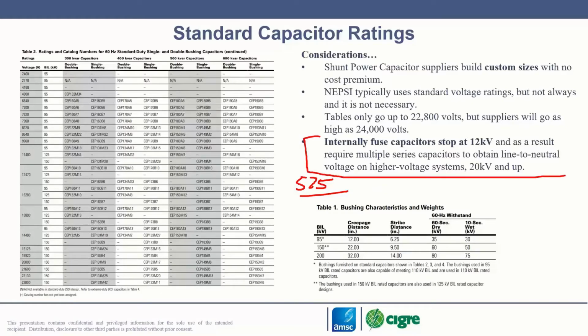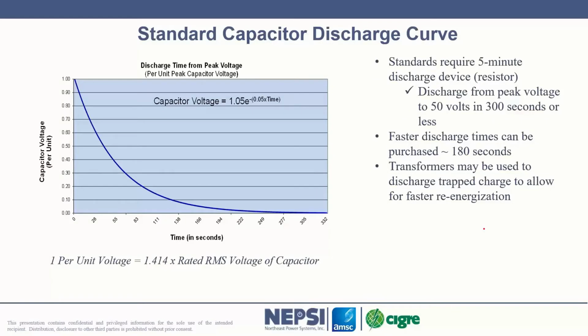Internally fused capacitors are interesting to note. Typically, we're dealing with voltages that stop at about 12 kV for the capacitor, which means that for higher voltage systems, typically those voltages up at the 23 kV level, we're going to be putting two capacitors in series to achieve the necessary voltage rating. So that's a key advantage of the single bushing externally fused capacitor: I can get to about 24 kV with an externally fused capacitor. With an internally fused capacitor, I must use two in series. So remember, just pick the kVAR and voltage rating you need, give that to the capacitor bank supplier, and they'll make it happen for you. And you're not paying much for that custom size capacitor.